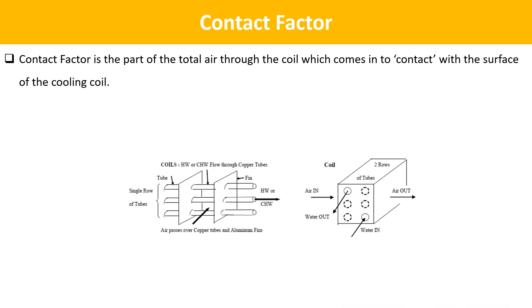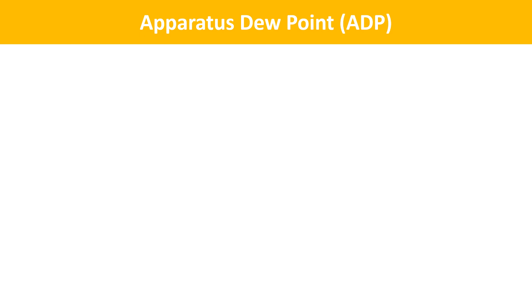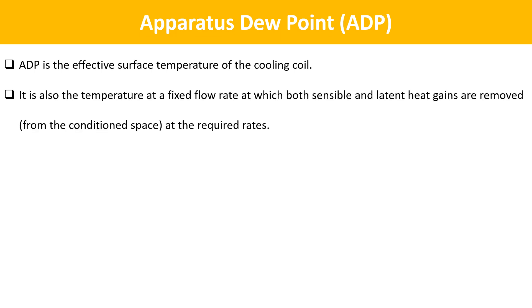The next term is Contact Factor. Contact factor is the part of the total air through the coil which comes into contact with the surface of the cooling coil. The next term is Apparatus Dew Point. ADP is the effective surface temperature of the cooling coil. It is also the temperature at a fixed flow rate at which both sensible and latent heat gains are removed from the conditioned space at the required rates. It is also often called the coil temperature.